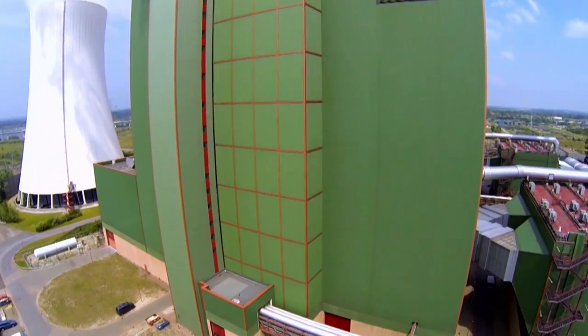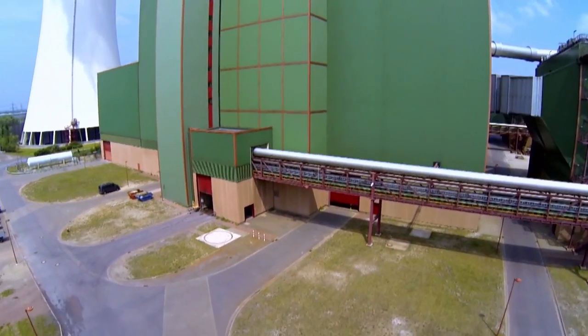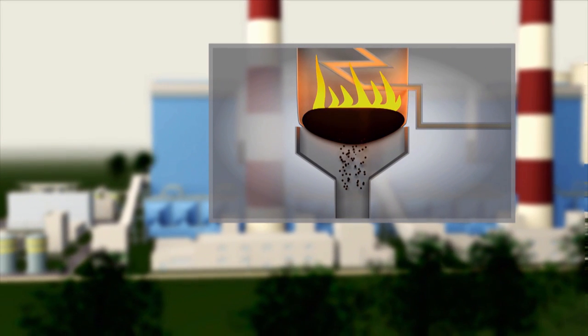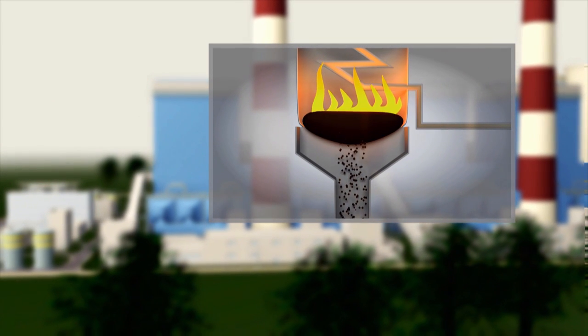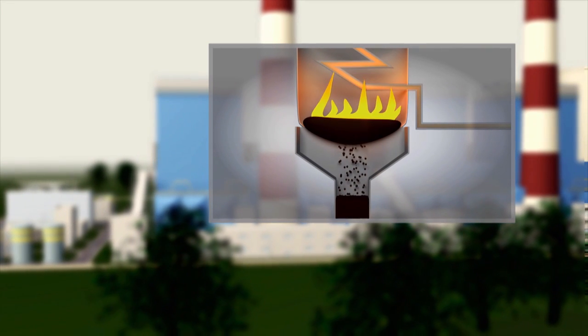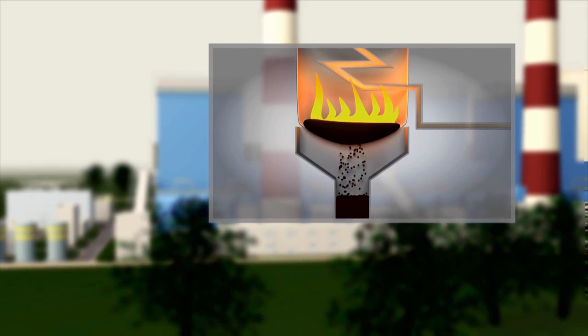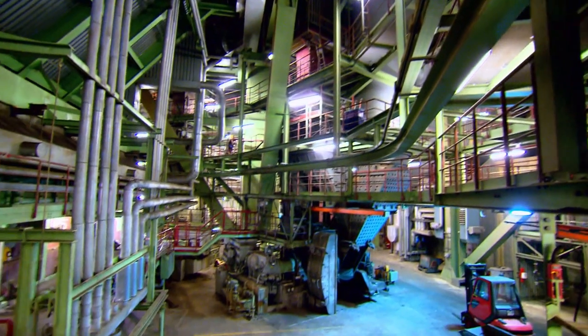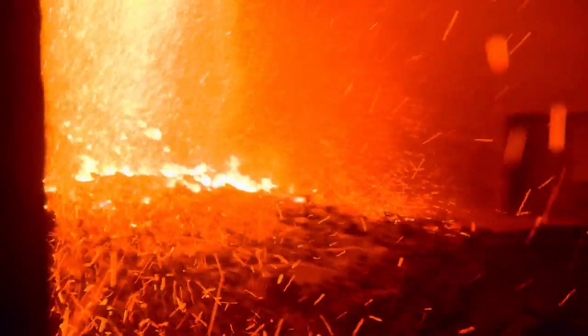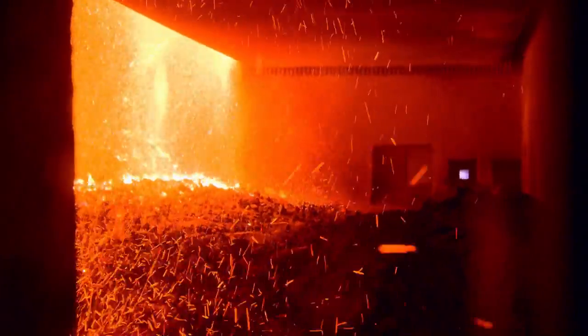Time for some explosive cleaning. There's an emergency in the boiler house next door. Where coal is burned, ashes are produced, and in a power plant this happens in the boiler. Normally the ashes fall down through a kind of funnel and can be removed, but sometimes the funnel gets clogged — and that's exactly what's threatening to happen at the bottom of the boiler. Once ash is lying on the grate as a large lump of slag, it's possible that the narrow shaft is simply too small.